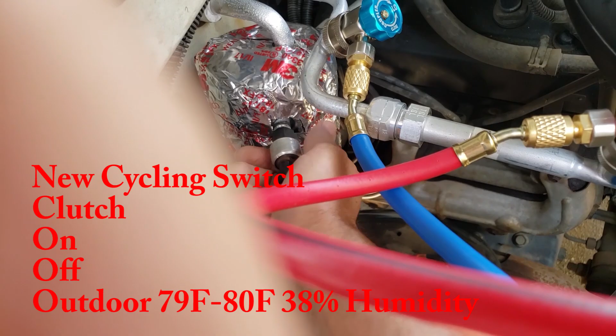Kicking the compressor on at 37 psi is still too low. It needs to go up to 44 to 46, I think, is ideal. Even though that's going to be a warmer evaporator, it's also going to give the evaporator time to get above freezing. So there's that to think about.